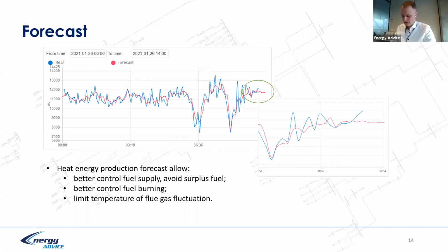Forecast. Of course, if we have flow consumption data, we can always forecast what the heat consumption will be. This example is from an industrial company where the boiler is installed and the random process is very active. I mean, heat consumption can stop rapidly and increase rapidly. It's quite an unstable process in an industrial company. However, we can forecast heat consumption quite well. For a utility which produces heat for a district heating company, it's probably an easier task and could be done with less error.